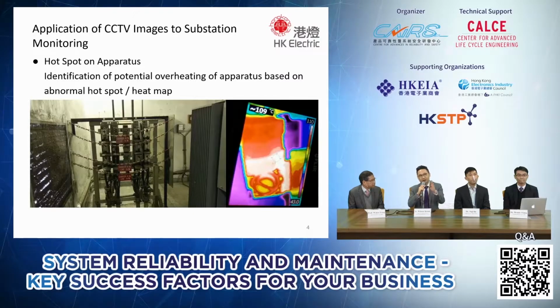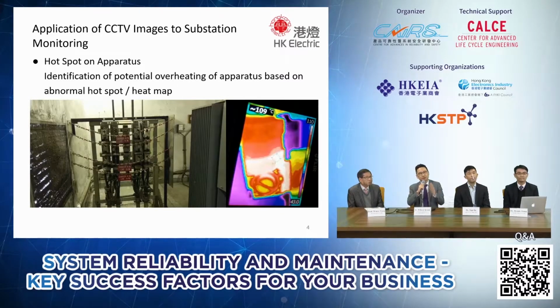For example, there are hotspots on the fuse panel, which is how we distribute energy to our customers. As time goes on, there may be loose connections in the fuse panel due to wear and tear or other reasons. If the connection is not good, by the law of physics, resistance will develop, and when current flows through, it becomes a hotspot. If the heat increases past a threshold, it may turn into a fire or burn the fuse panel, affecting power supply to our customers.